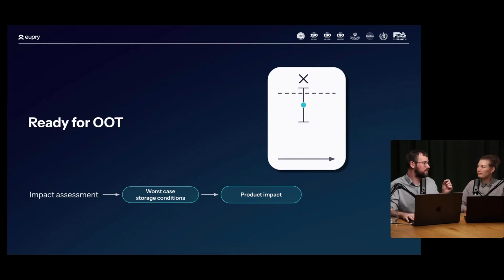Normally, it's way less, but for the sake of experiment. So would you have to account for the drift set by the supplier for the sensor? When we get a calibration result that is out of tolerance, we already know what the drift was. We just compare the last calibration with the calibration we have now, and then theoretically it could have gone up and then back down to the point. But in most cases, drift is never going to go up and down. It tends to go in one direction.